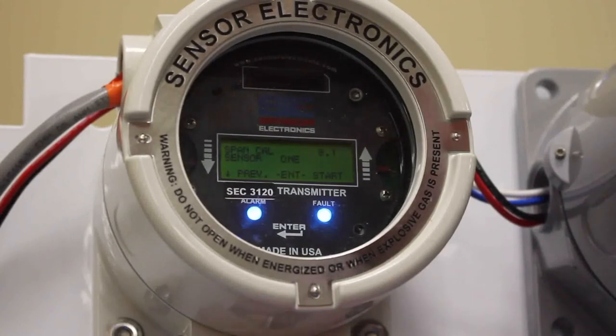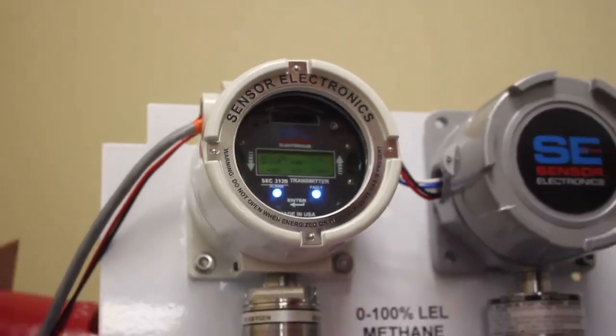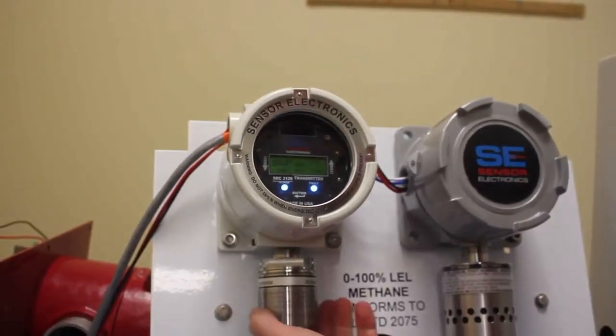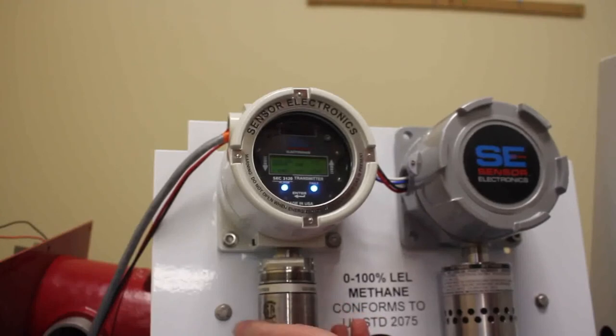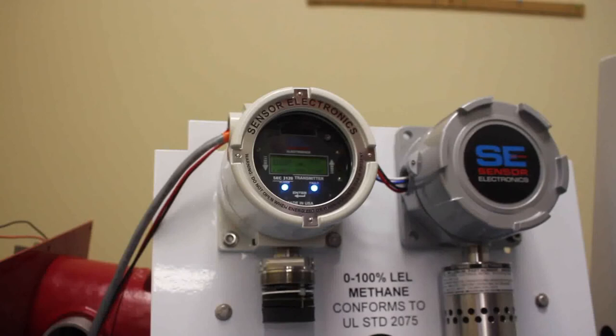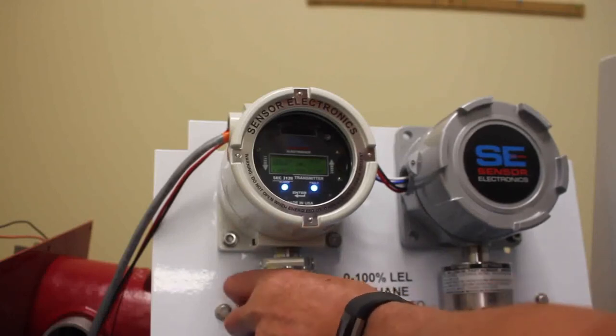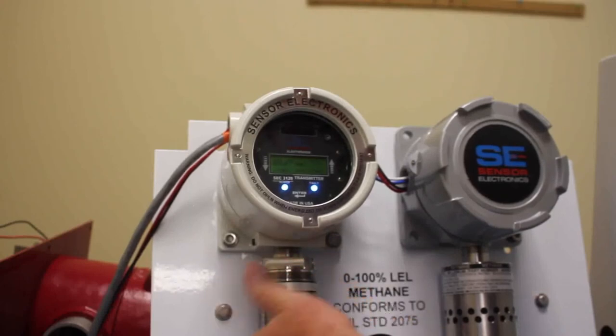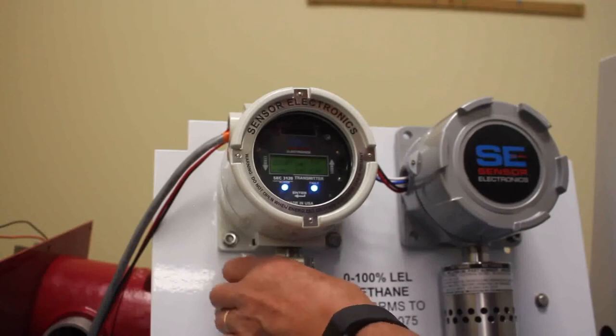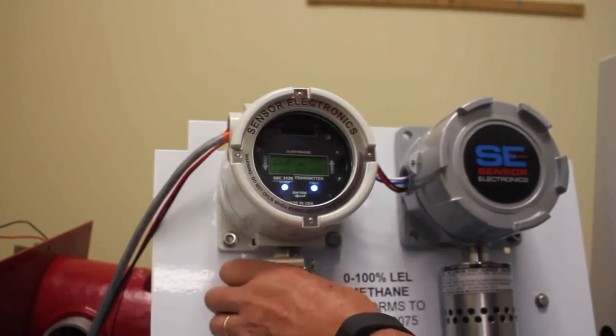If you ever need to replace the sensor, you would just unscrew this cover, and that would allow you access to the sensor element. It also helps if you unscrew the cover to release some of the nitrogen that's trapped in the sensor housing from the previous calibration, the zero calibration. So we've allowed the oxygen to get back up into the sensor, and we just screw the cover back on. So normally I could say the ambient air contains 20.9 or 21% by volume oxygen.